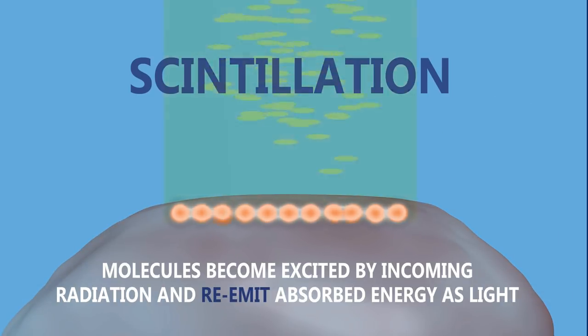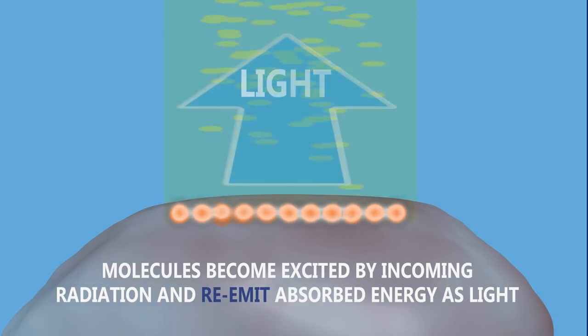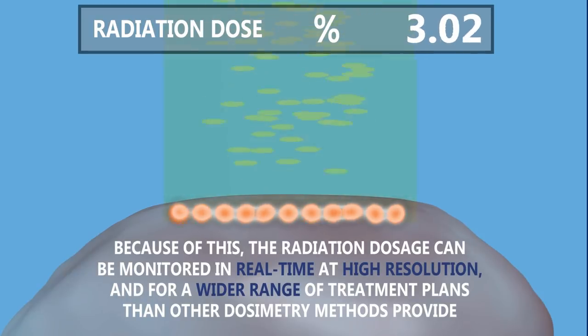Scintillation refers to the process where molecules become excited by incoming radiation and re-emit absorbed energy as light. Because of this, the radiation dose can be monitored in real time, at higher resolution, and for a wider range of treatment plans than other dosimetry methods provide.